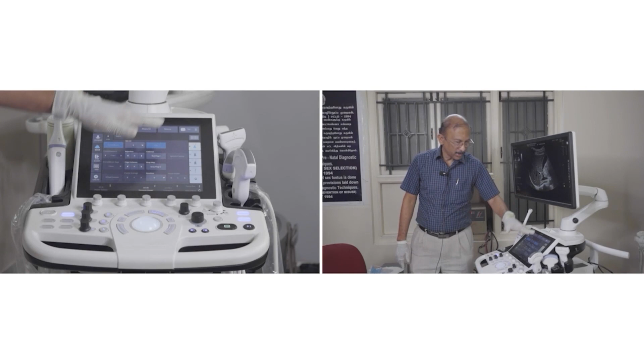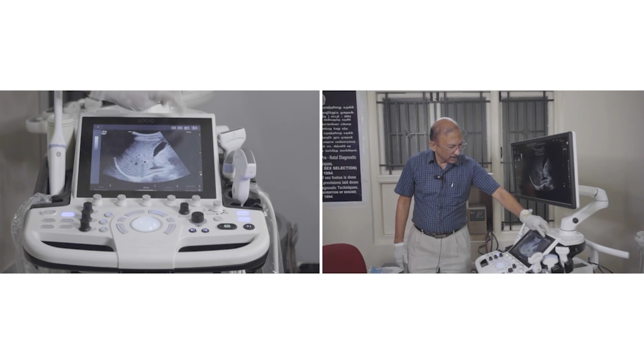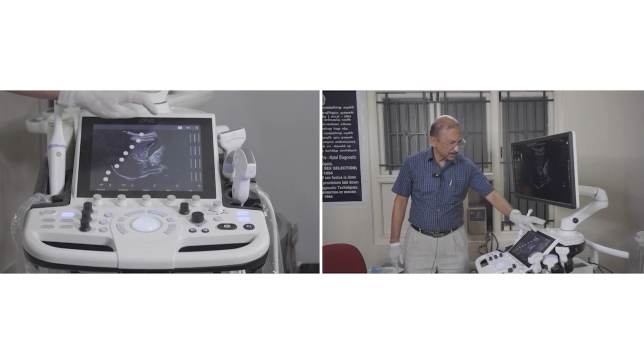Now I am coming down to the touch panel. The touch panel which really impressed me is the mirror image. You can just see the images on the mirror monitor as well as the image here. If I feel the brightness is not sufficient, I can always increase it. Then, by even the TGC adjustment, if I feel the posterior enhancement is not sufficient, if I want to increase the posterior gain, I can increase it, or I can change it to any level by adjusting the TGC curve.